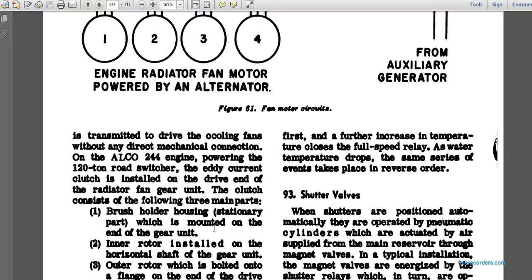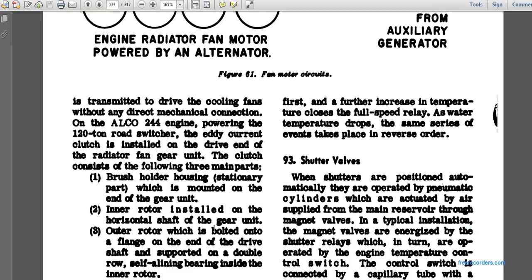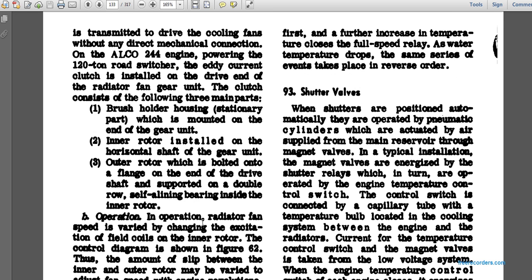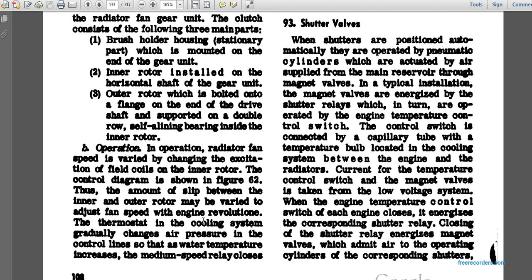The clutch consists of three main parts: a brush holder and stationary part mounted on the end of the gear, an inner rotor installed on the horizontal shaft of the gear unit, and an outer rotor bolted to the flange of the driven shaft, supported on a double-row self-aligning bearing. The operation of the radiator fan speed is verified and varied by changing the excitation of the field coils on the inner rotor. The control diagram is shown in figure 62.